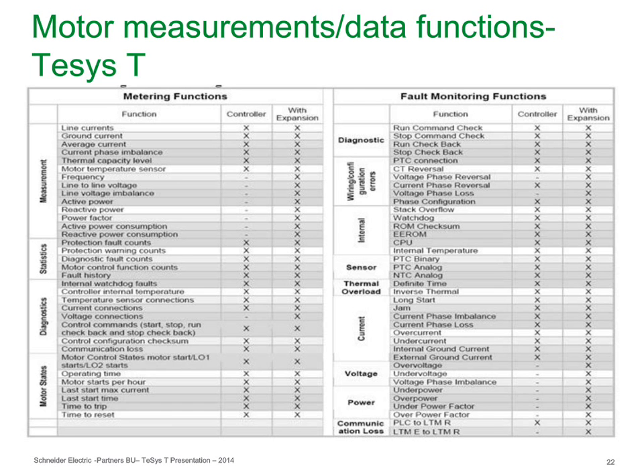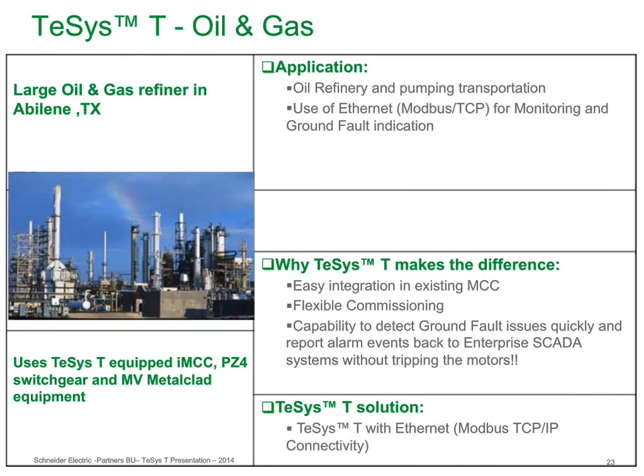So you've seen a lot of information here. What I want to tell you here, you say, well, does this really come together to be of value for me? And I'm going to tell you about an application that was recently sold through our Graybar location near Abilene, Texas. This is for a large oil and gas refinery that is in that area. And we've recently installed a large installation of intelligent MCCs that have TeSys T, along with some switchgear and some medium voltage equipment. But the big reason that they chose the Schneider Electric TeSys T product for this had to do with its ability to detect ground fault issues, but separate the ground fault in an alarm from the tripping functions.